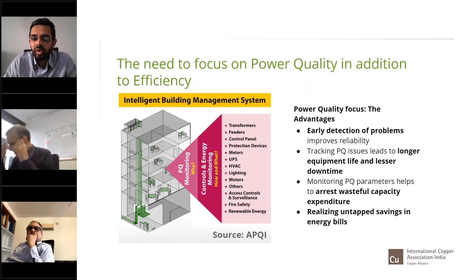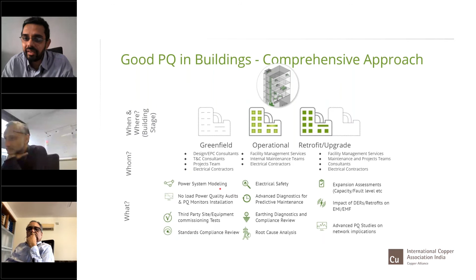To integrate power quality into the life cycle of a facility, there are different facets — it can start from the greenfield stage through operational to retrofit, with various things in the power quality ecosystem you can take up to enable a much better design system. For example, through power system modeling you can accurately model the impact of transformer inrush and harmonic analysis to avoid surprises later. More importantly, it helps in studying fault levels and designing coordination of the entire system to act as desired in fail-safe as well as normal operating scenarios.